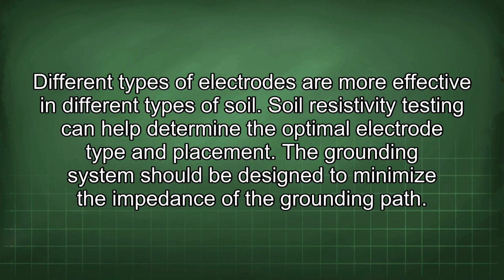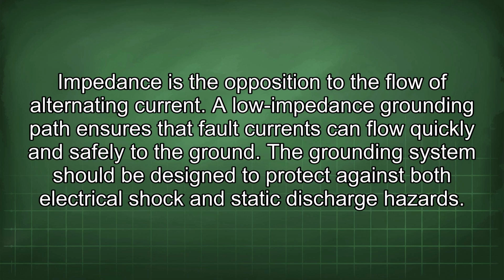The grounding system should be designed to minimize the impedance of the grounding path. Impedance is the opposition to the flow of alternating current. A low impedance grounding path ensures that fault currents can flow quickly and safely to the ground.